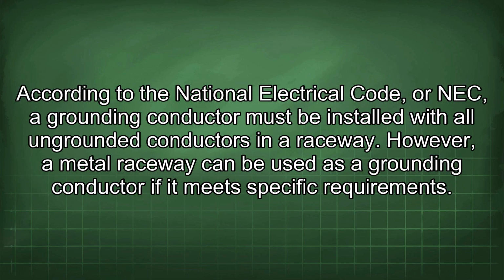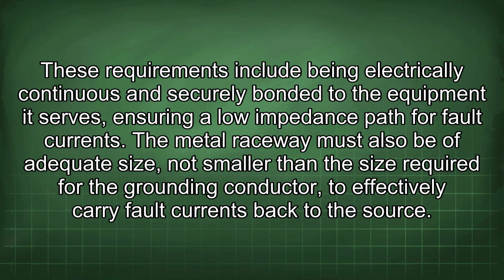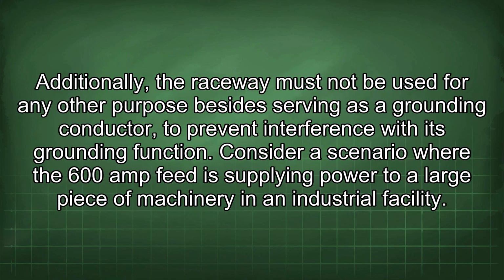According to the National Electrical Code, or NEC, a grounding conductor must be installed with all ungrounded conductors in a raceway. However, a metal raceway can be used as a grounding conductor if it meets specific requirements. These requirements include being electrically continuous and securely bonded to the equipment it serves, ensuring a low impedance path for fault currents. The metal raceway must also be of adequate size, not smaller than the size required for the grounding conductor to effectively carry fault currents back to the source.